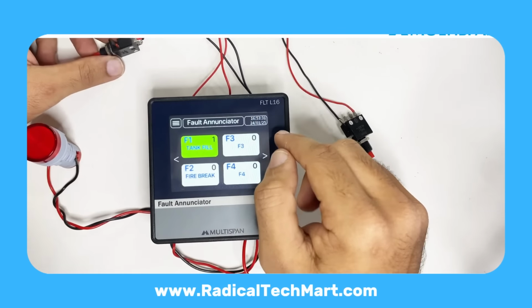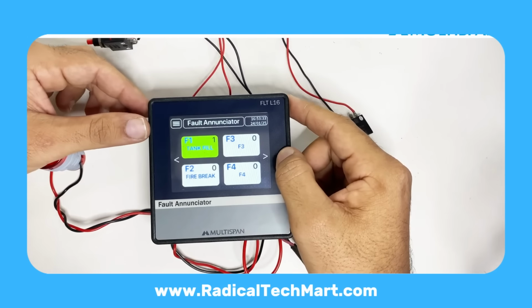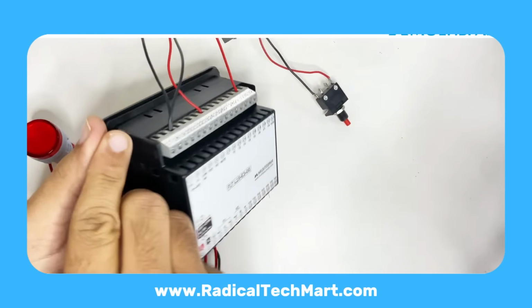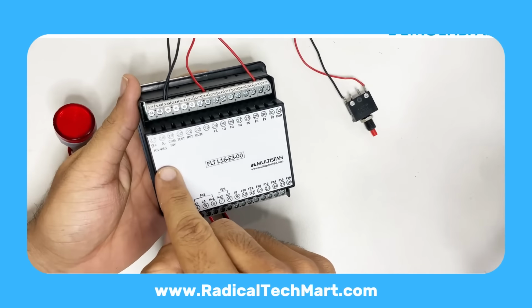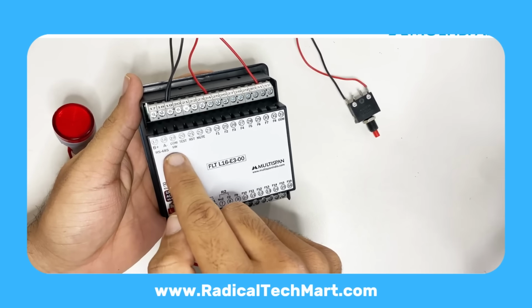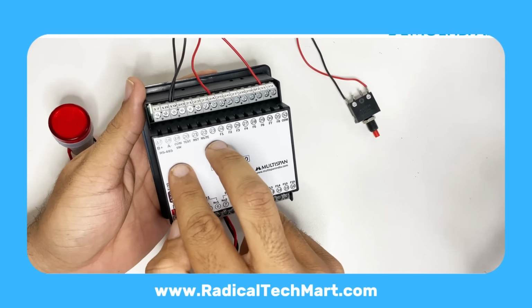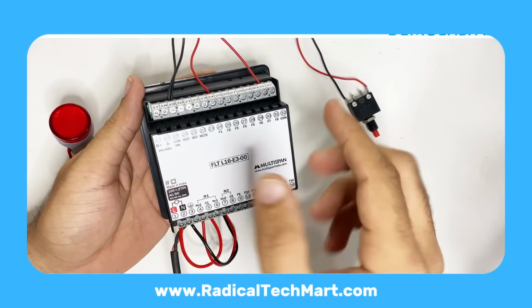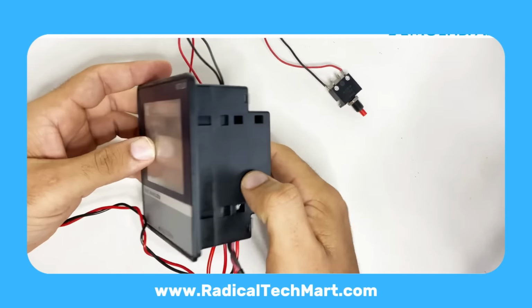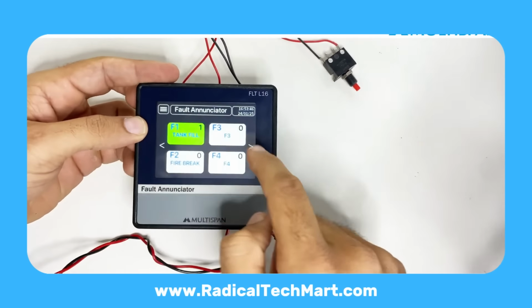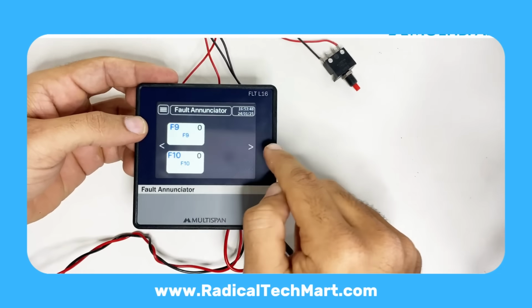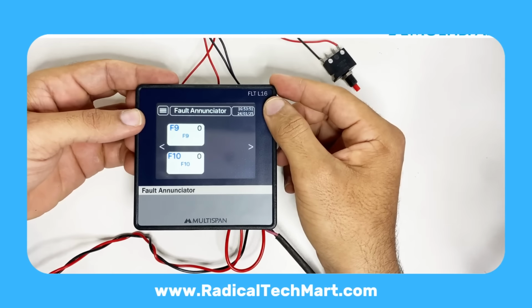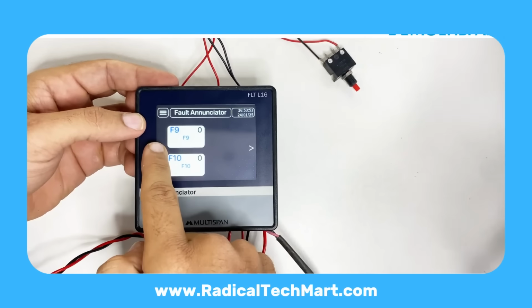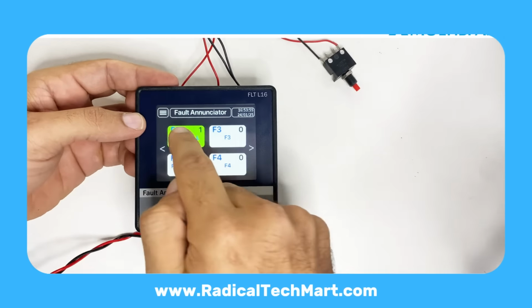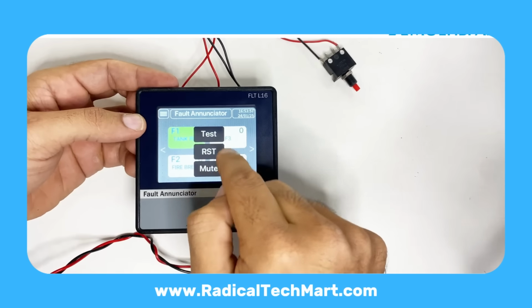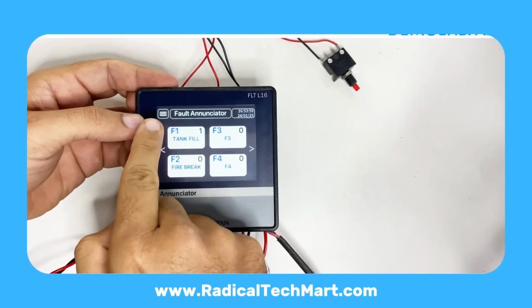If you do not want to come to the panel to mute, there is also an option to mute from the field. On the back side, we've provided terminals for a remote mute push button. You can connect an NO-type switch between the mute input and common. Operators in the field can then acknowledge or mute the alarm without going to the main panel. If you have, say, 10 fault channels configured, any one of them receiving a fault will immediately pop up on the first page of the screen so it is easily noticed.